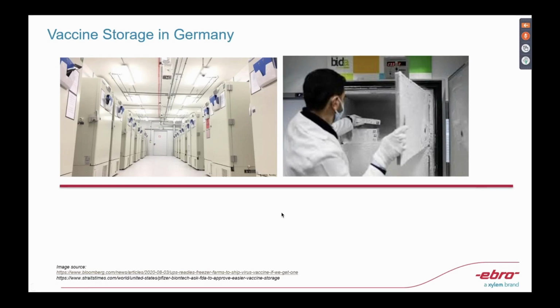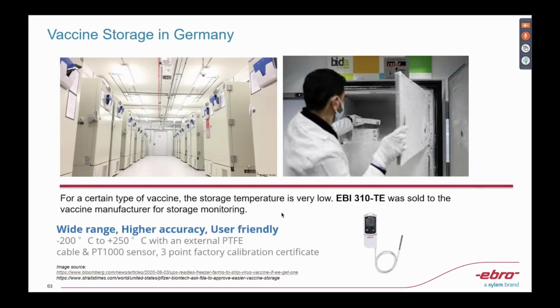Here's another example: vaccine storage in Germany. A famous vaccine manufacturer there bought our EBI 310 TE for storage monitoring. I think one reason they chose our data logger is because it's very easy to use. You don't need to open the freezer; you can just remove the main device for measuring, reading out the data, doing the programming, and reading out the value. The sensor can stay where it is. You don't need to remove the entire data logger from the chamber.